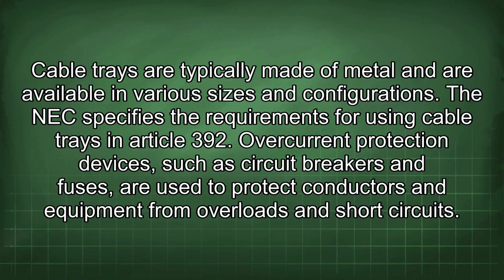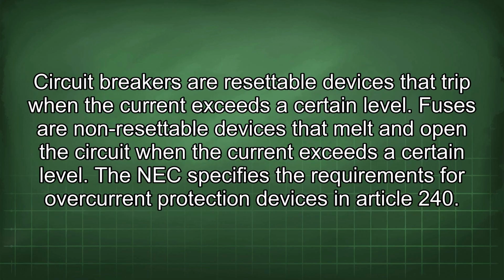Overcurrent protection devices, such as circuit breakers and fuses, are used to protect conductors and equipment from overload and short circuits. Circuit breakers are resettable devices that trip when the current exceeds a certain level. Fuses are non-resettable devices that melt and open the circuit when the current exceeds a certain level. The NEC specifies the requirements for overcurrent protection devices in Article 240.